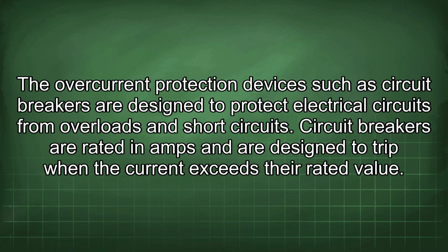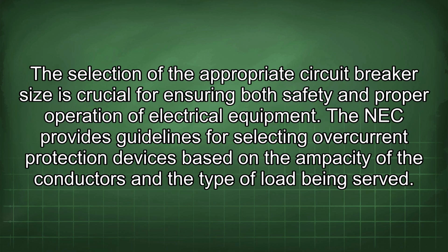The overcurrent protection devices such as circuit breakers are designed to protect electrical circuits from overloads and short circuits. Circuit breakers are rated in amps and are designed to trip when the current exceeds their rated value. The selection of the appropriate circuit breaker size is crucial for ensuring both safety and proper operation of electrical equipment.